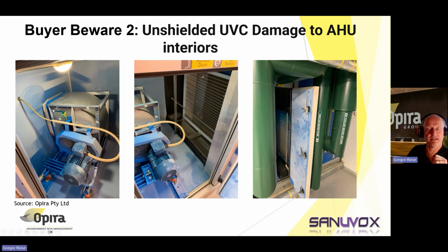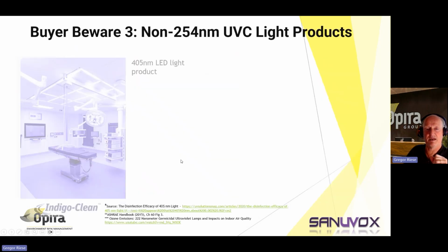There's also damage inside the air handling units with unshielded lamps, and that certainly is a consideration for the powder coating, as well as any plastic products such as this unshielded power supply to the fan here. So some damage happening there.